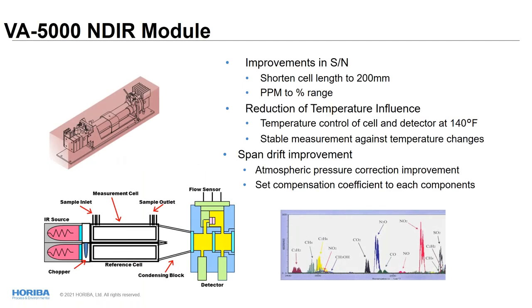All right, let's talk about some technical information, how we measure those parameters. The VA-5000 uses the NDIR measurement method. NDIR covers from the ppm level to percentage. We keep the measurement cell at 140 degrees F, keeping the cell warm. This helped improve the measurement result. Ambient temperature change is one of the big factors in the fluctuation of the measurement value. So keeping the cell warm is one way to avoid the effect of temperature changes.